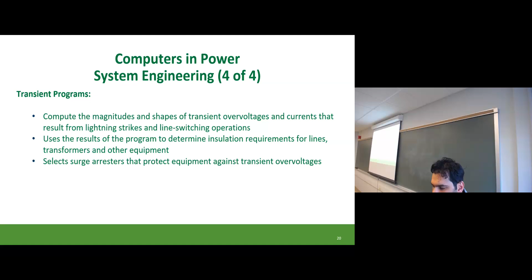Transient programs are used to study the system during very large disturbances, like a switching event or a thunderstorm. We look at how the system operates at that moment and what protection measures should be taken against overvoltages. For example, surge arresters protect equipment against transient overvoltage—you'd run a transient program to make sure the rating of that surge arrester is good enough to handle such a large overvoltage or transient.